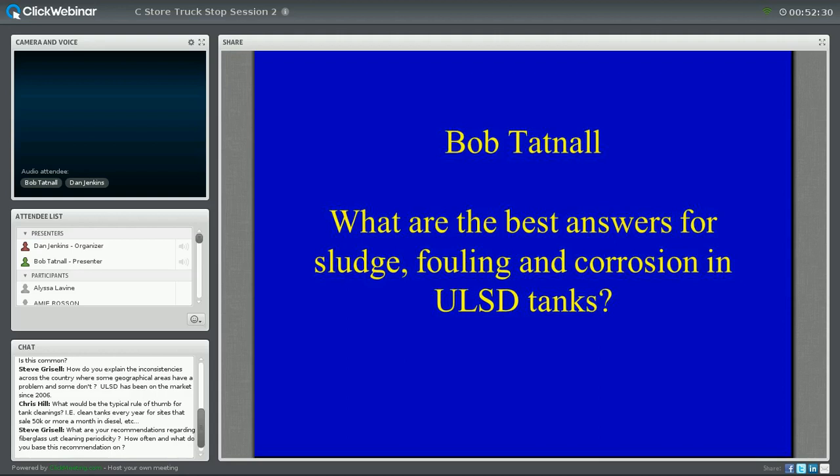I was looking at this gas station chain, and they asked me to look at some of their suppliers' facilities and see if that was a problem. They gave me the names of 3 different terminals that they bought from. This was in the state of Mississippi. And in that area, they used 3 different terminals. And so we visited all 3. One of them was clean as a whistle. You know they did everything right. You know they drew the water off the bottom of those tanks weekly like they were supposed to. It would just run like a tight ship.